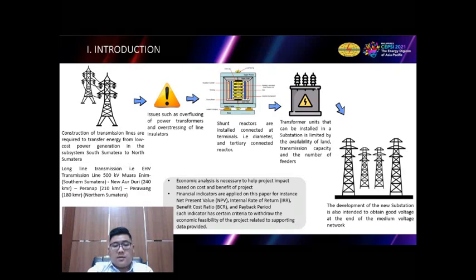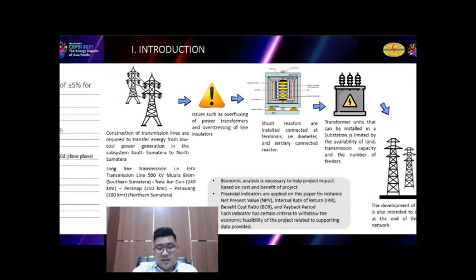Issues such as overfluxing of the power transformer and the overstressing of the line insulator would be a concern. Shunt reactors are installed connected at the terminals, for example, diameter and tertiary connected reactor. Transformer units that can be installed in the substation are limited by the availability of the land, transmission capacity, and the number of the feeder. The development of the new substation is also intended to obtain good voltage at the end of the medium voltage network. Economic analysis is necessary to help project impact based on costs and benefit of the project.